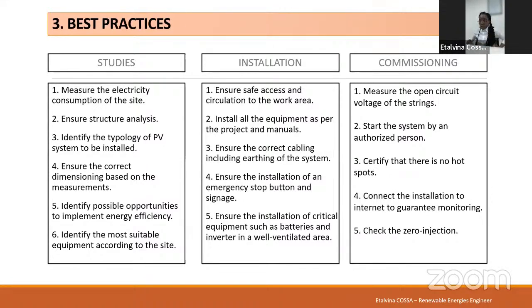In the commissioning, first we have to measure the open circuit voltage of the strings to avoid damage in the inverter. In some cases we have the trackers, the MPPT inside the inverter, so we have to avoid connecting the strings without measuring the voltage.